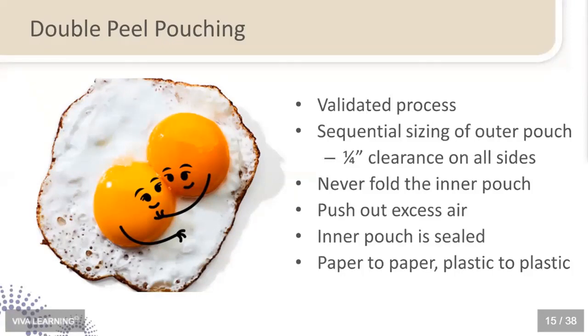It also cannot be oversized. You can't use a 3.5 by 11, a 3.5 by 9 pouch and put it inside a 10 by 14, because there's going to be problems with penetration of the sterilant and also getting out the steam at the end of the cycle. So they need to be sequentially sized.